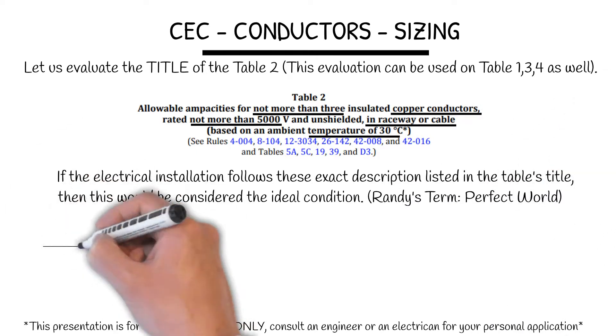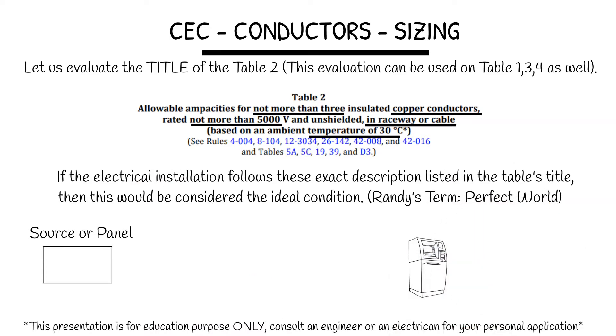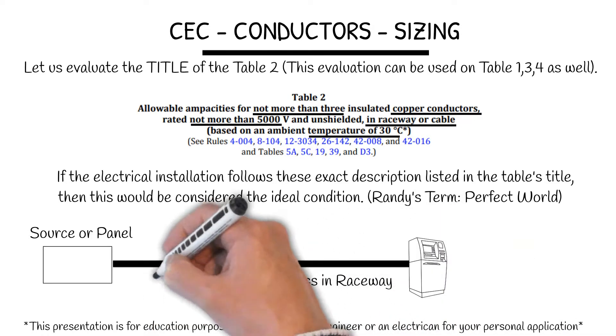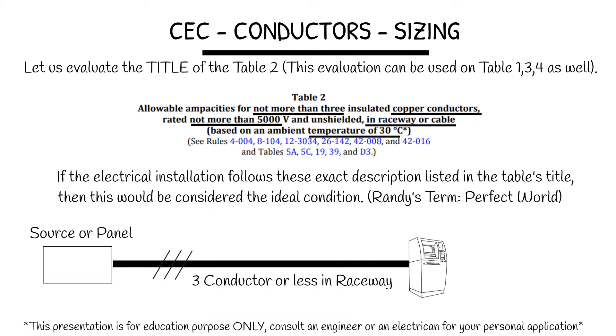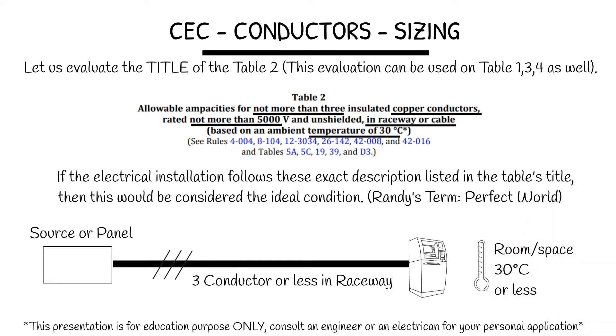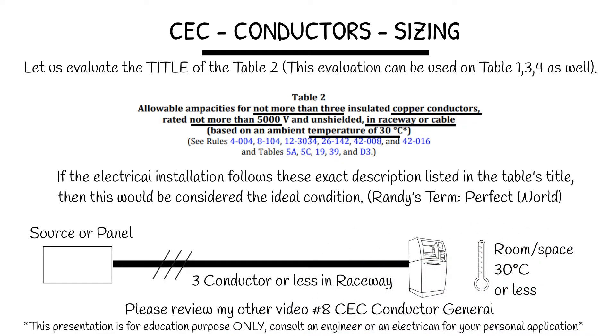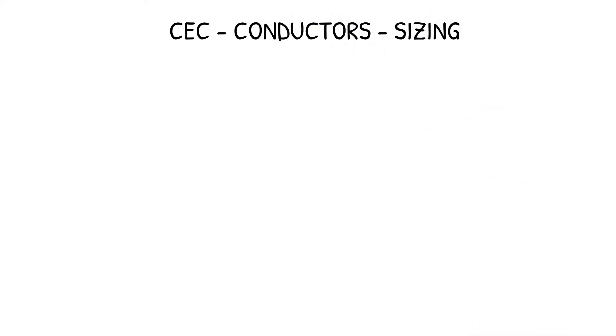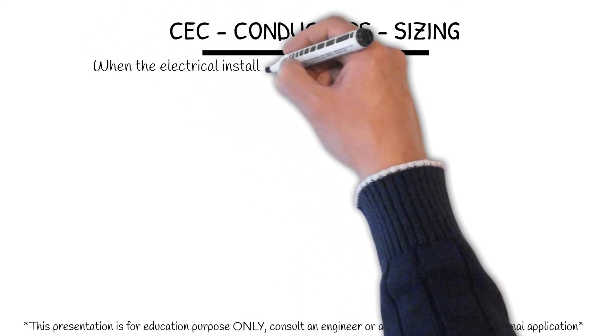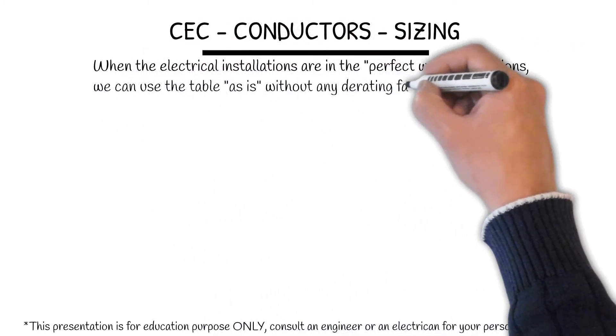Why call it the perfect world? You have 3 conductors or less in the raceway, and the room or space temperature is 30 degrees or less. Please review my other videos, number 8, CEC Conductor General. When the electrical installations are in the perfect world conditions, we can use the table as is without any derating factors.